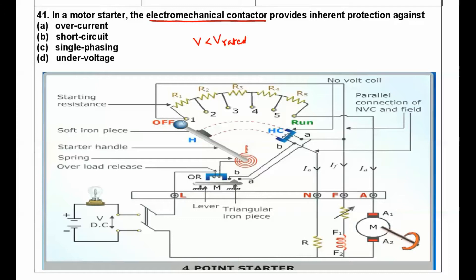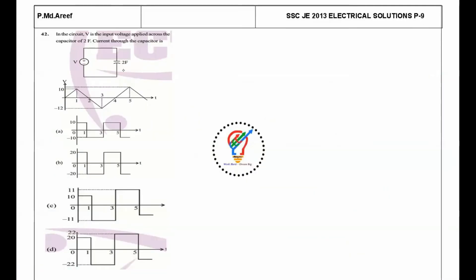When you want to start the DC motor, we will move this starter handle like this. At this point, whenever there's a low voltage condition or power failure condition, the holding coil releases this soft iron piece and the starter handle will revert back. So the answer is under-voltage or low voltage condition.